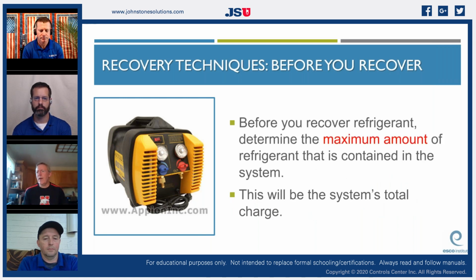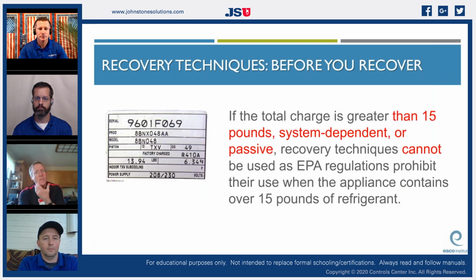Before you recover refrigerant, determine the maximum amount of refrigerant that's contained in the system. This is probably going to be on the nameplate.